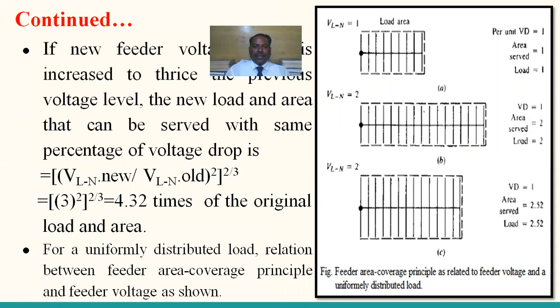for design consideration of the primary feeder. And similarly, the primary feeder is also designed based upon the feeder loading. Already I told that the primary feeder exists between the substation and the primary of the distribution transformer. So the load is uniformly distributed throughout the length of the line. Therefore the design considerations are based upon one, the voltage level, and another, the feeder loading. Feeder voltage levels are discussed so far, and feeder loading is to be considered next.